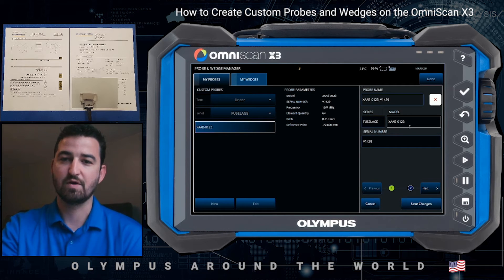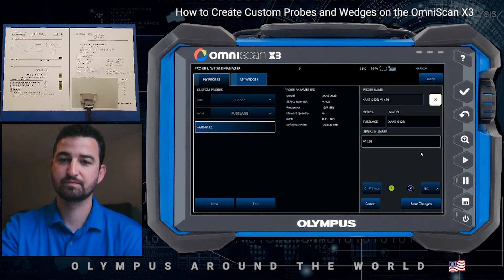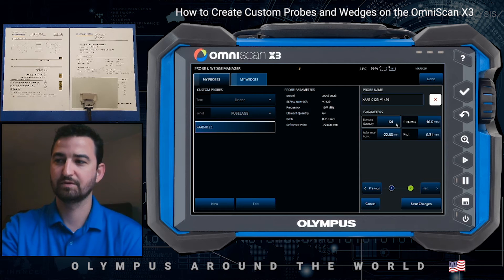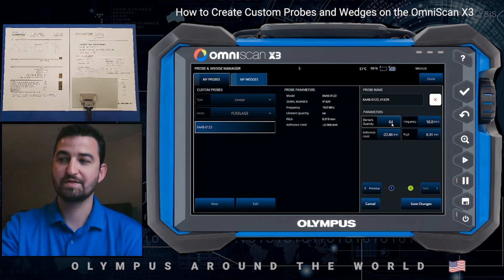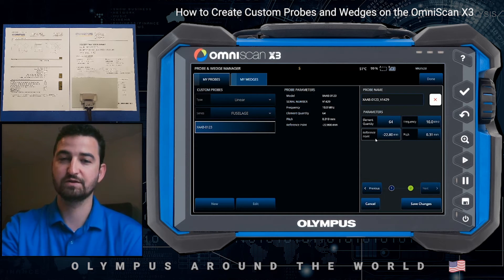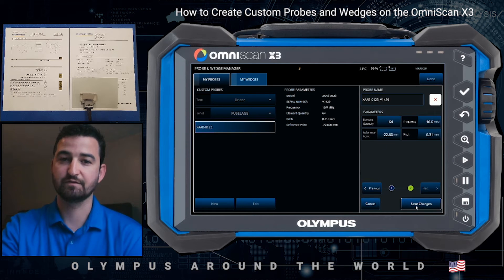The model and serial number are provided on the datasheet. You hit next. You add the element quantity, frequency, reference point, and pitch. And hit save.